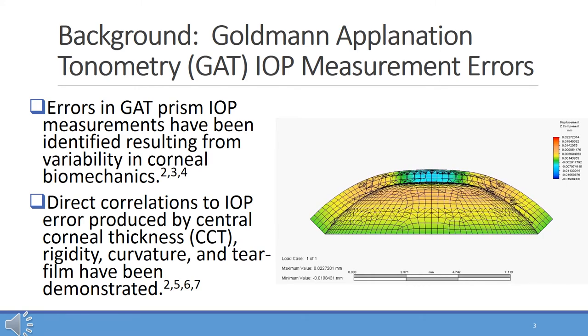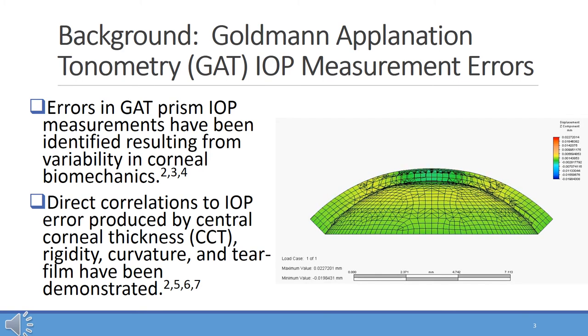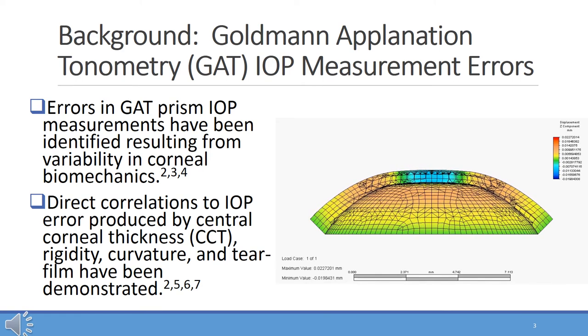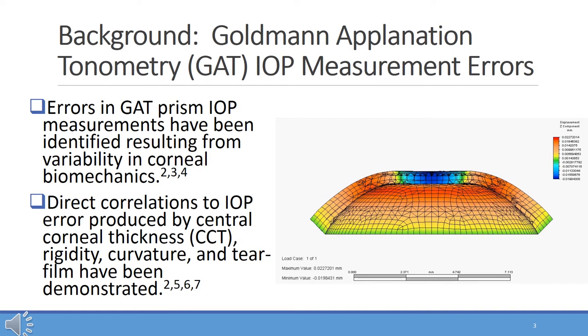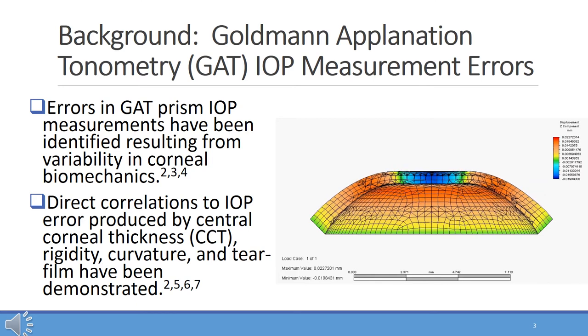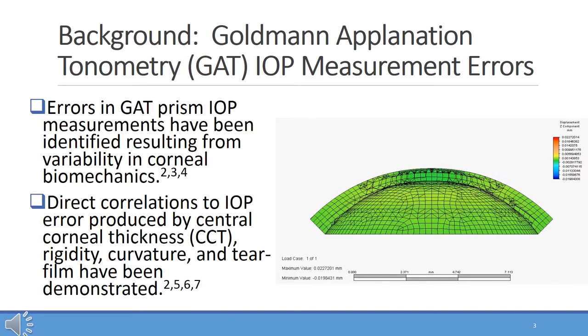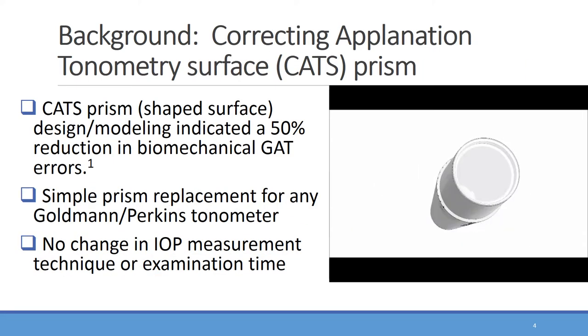It has been demonstrated over many decades of publications, and even mentioned by Goldmann himself 60 years ago, that several IOP measurement errors are present. Those errors include corneal biomechanical errors of central corneal thickness, corneal rigidity, as well as corneal curvature, and separately the corneal tear film adhesion force — primarily in the Goldmann prism contact surface.